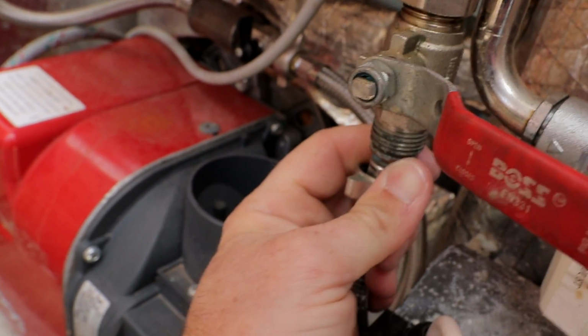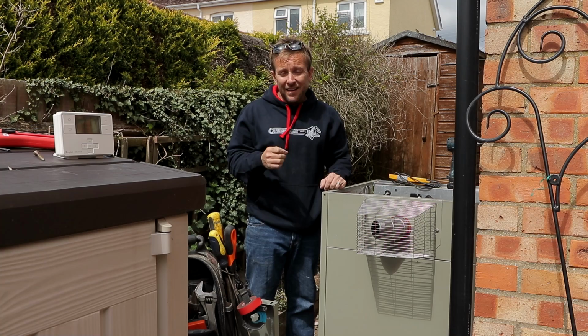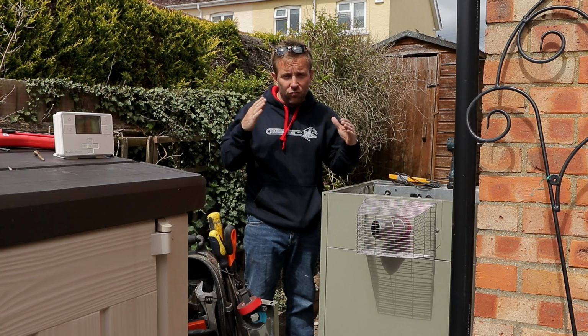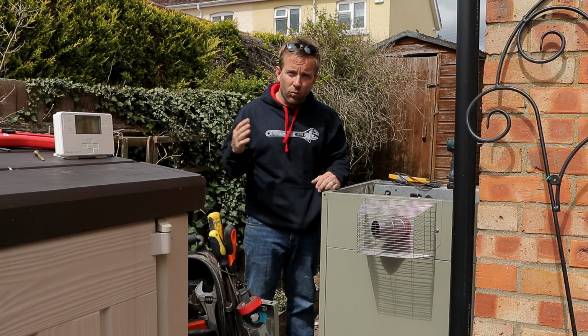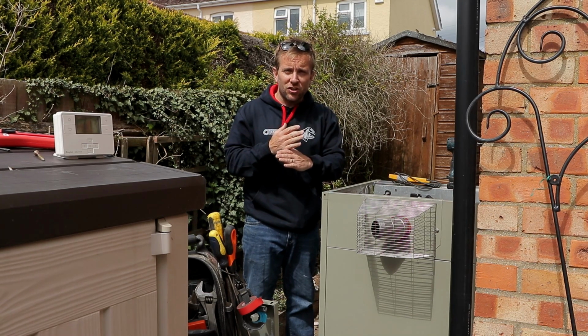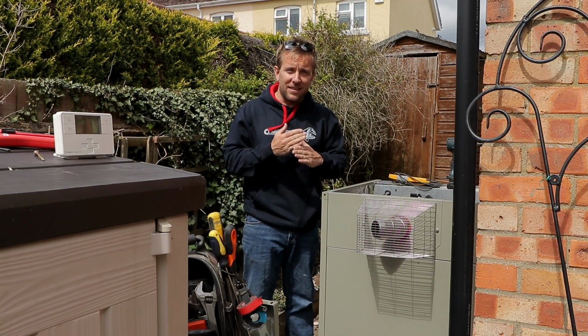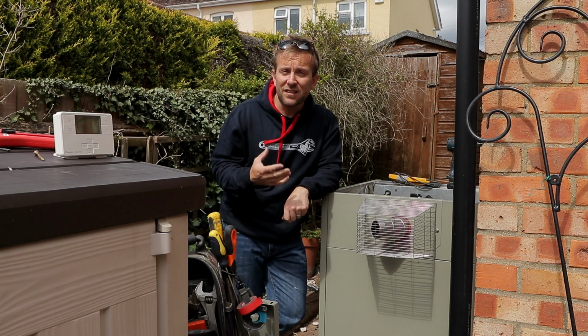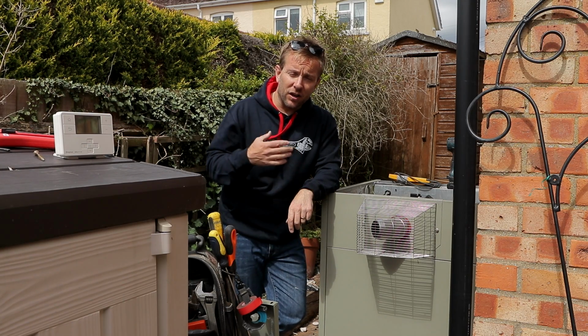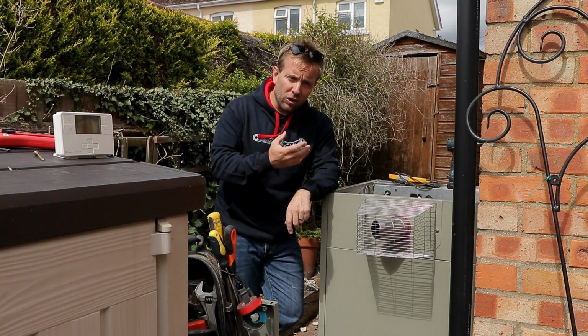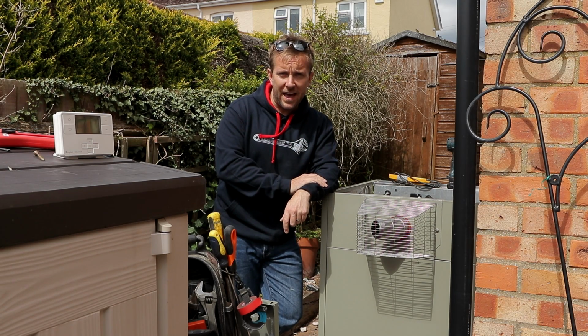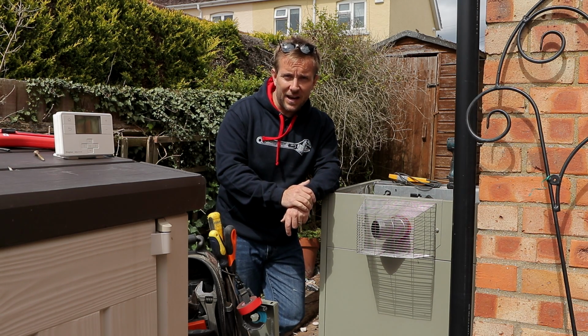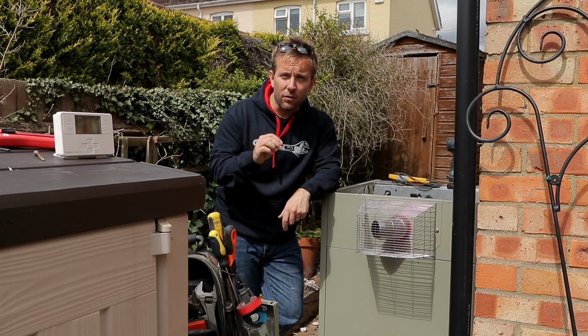If we're still seeing a rise in pressure after that, then there's only one place those two can cross over - where our mains water pressure in and our system pressure can cross over - and that is within the heat exchanger. So I'm going to leave this another 5 or 10 minutes, then go back to my phone and look at the photo. If I've still got that problem, then I know this is probably going to be a heat exchanger, and that's the first thing I'm going to change.